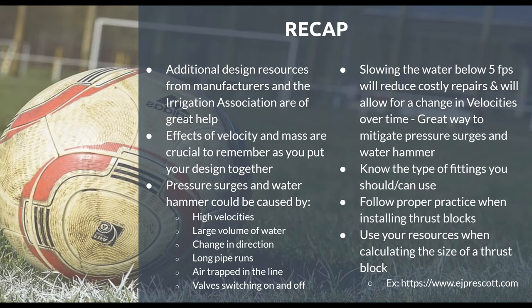There is actually an irrigation manufacturer that has designed a valve that, when a water hammer situation occurs, the valve actually opens up for just a second or so and will disperse that energy downstream — into where the sprinkler heads are — and then that air can be exhausted. A lot of times on irrigation systems using this particular valve, when one zone is coming on and another is going off, another zone way out there somewhere would just kind of pop up the rotors for just a second and come down. That particular valve is actually expelling that energy to the downstream side.